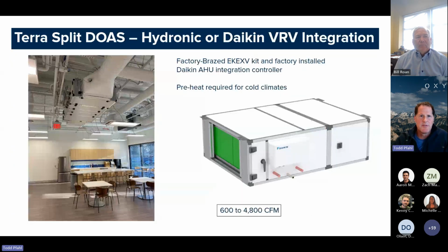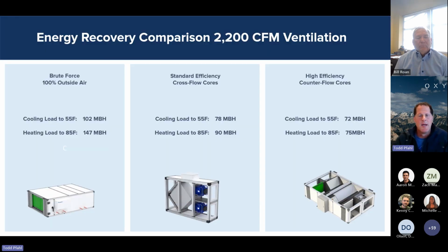And then an example of just using 100% outside air. So this would utilize a Daikin VRV where we have the controller and the EKEXV expansion valves installed in there. And then we have room neutral condition at 70 degrees, 50% RH that's fed into, in this particular example, the VRV cassettes, or we could put it directly into the space via diffusers or backup fan coils, air handlers, whatever is needed.